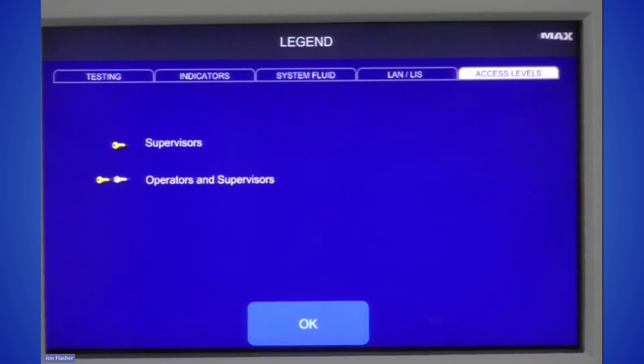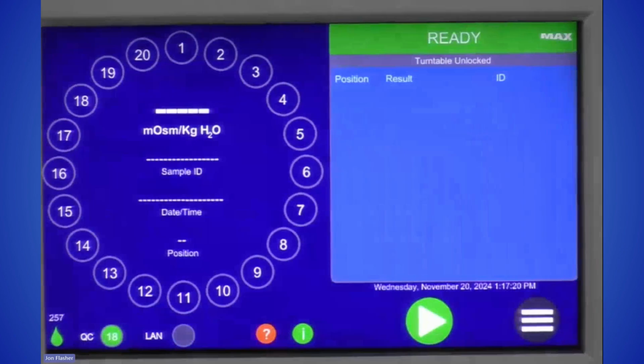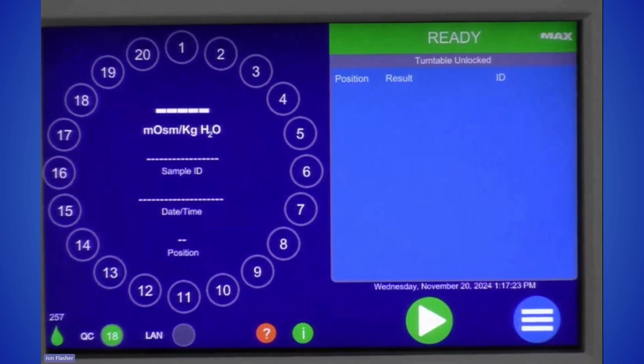This last tab, where it says access levels, is an indication of what you can access, change, or perform on the instrument, depending on your user profile. The little gold key is for supervisors only, and the gold and silver keys are for operators and supervisors. That's a neat new feature that allows you to pre-program user profiles and user permissions for folks in your laboratory ahead of actually using the instrument. So a great feature there.